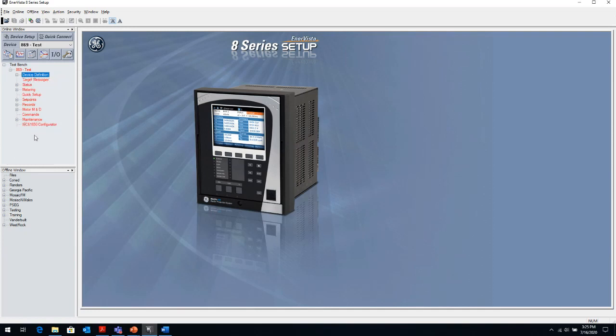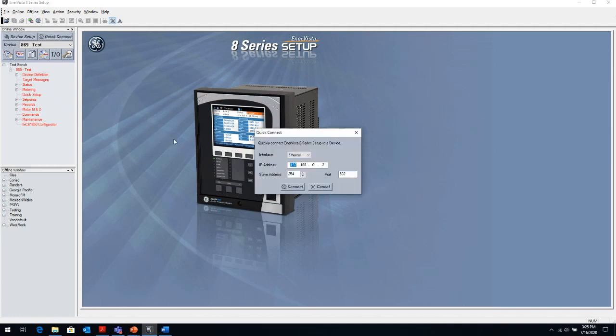So when we come into the online window, there's a couple of things that are important to note. So first of all, before we talk about those elements, is how do I connect to the relay? There's a couple of ways to connect to the relay. One is the quick connect, and obviously, as the name suggests, is the quickest way to connect to the relay. So if I click on the quick connect, there's a number of ways to connect to the 8 series. There is the USB front port, which all you need is a device USB cable. It's exactly the same cable as your printer cable, so you can get this Amazon, Best Buy, wherever, it's a commonly available cable. You can connect through Ethernet. The 8 series can have from 1 to 2 Ethernet ports, but 2 Ethernet ports comes with the advanced communication module.